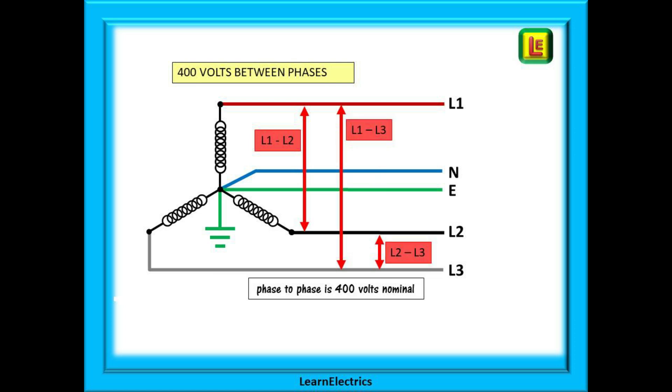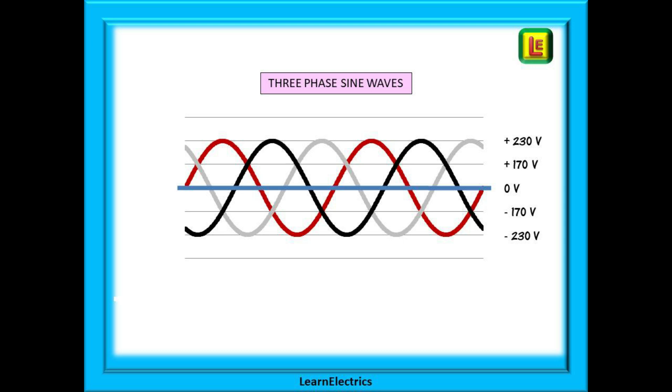If we ignore the neutral and measure across two of the phases we will have 400 volts. The voltage between any two phases, L1 to L2, L1 to L3 or L2 to L3 will always be 400 volts nominal in this system. The question then is, if a single phase is 230 volts, then why, across two phases, is it not 2 times 230, which is 460 volts?